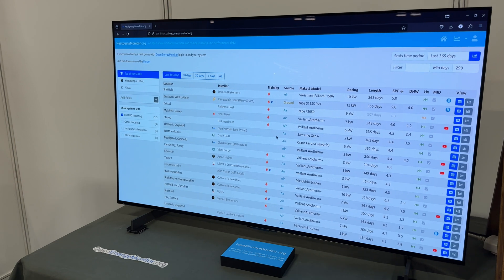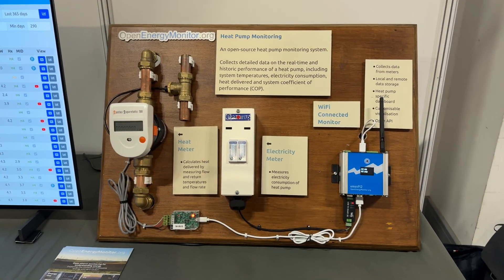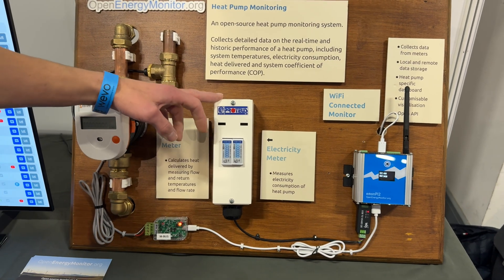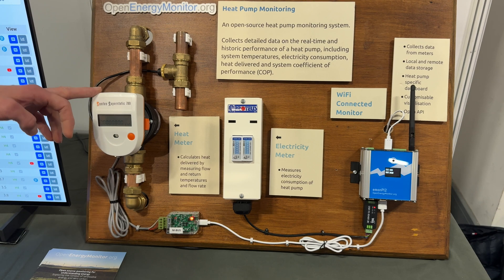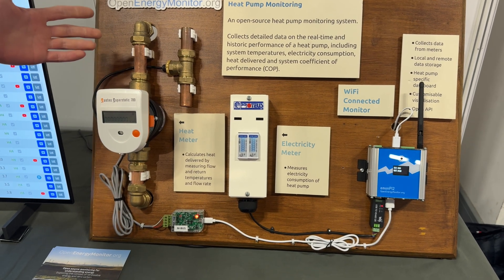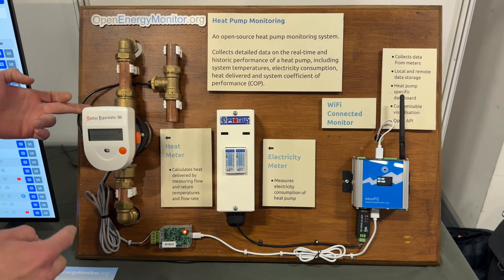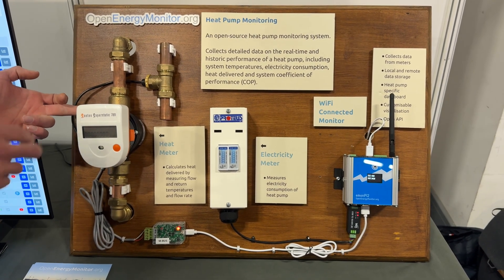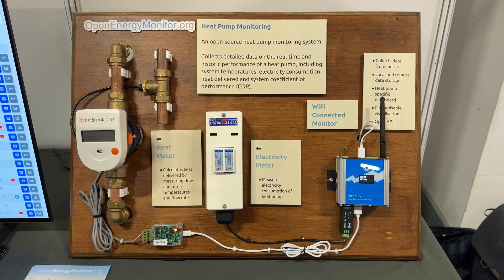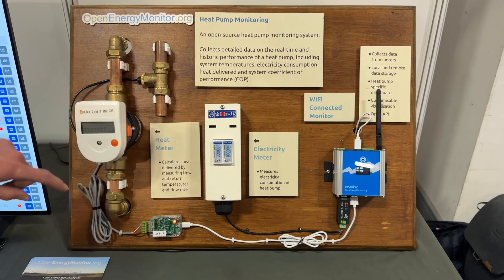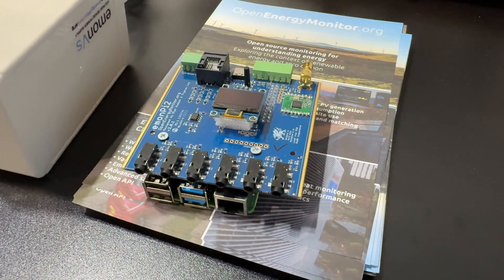You need a heat meter installed for this, don't you? Yeah. This is the hardware behind that data. We monitor the electrical input into the heat pump with one or two electricity meters, and then we monitor the heat output with a heat meter. These work by measuring the speed of flow of the water around the system and also measuring the temperature — a temperature probe on the flow, and a temperature probe on the return. If you know the temperature difference between flow and return and the flow rate, you can calculate the heat output. We read that with one of our data loggers by MBUS and Modbus.